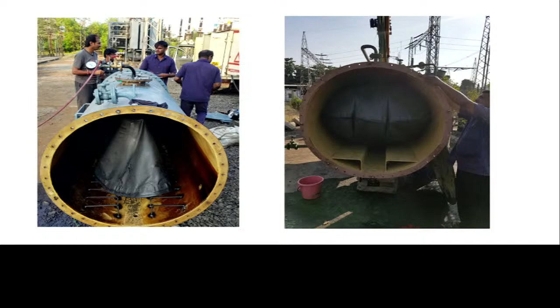The MOG, magnetic oil level gauge, whatever it shows, you are just believing, okay, 1/3 is 1/3, 2/3 is 2/3. It is not like that. Better you drain out the oil completely, measure the volume of the conservator, and if it is for 4 kL, you fill around 6 drums of oil in it, if the total capacity is 4000 liter. This way you can correct the air cell. This is very critical. It looks small, but in most cases, maximum complaints we get are that in summer when oil volume increases, there are maximum trippings in PRV, then leakages start because of improper breathing. If care is not taken here, it will start the leakages.